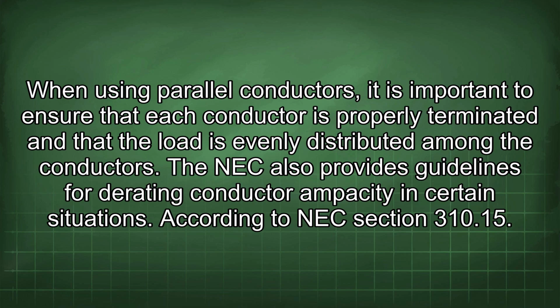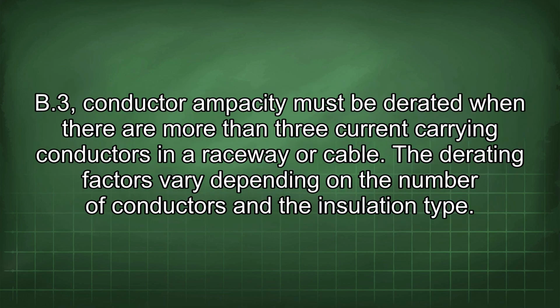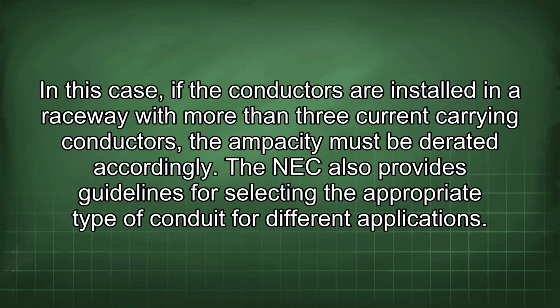The NEC also provides guidelines for derating conductor ampacity in certain situations. According to NEC Section 310.15(B)(3), conductor ampacity must be derated when there are more than 3 current-carrying conductors in a raceway or cable. The derating factors vary depending on the number of conductors and the insulation type. In this case, if the conductors are installed in a raceway with more than 3 current-carrying conductors, the ampacity must be derated accordingly. The NEC also provides guidelines for selecting the appropriate type of conduit for different applications.